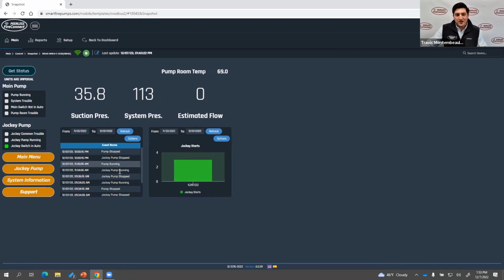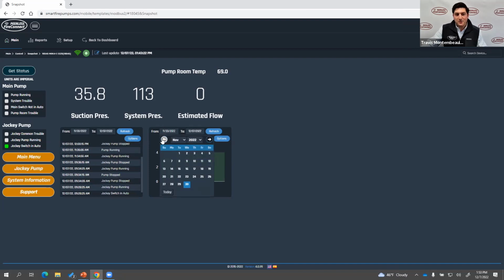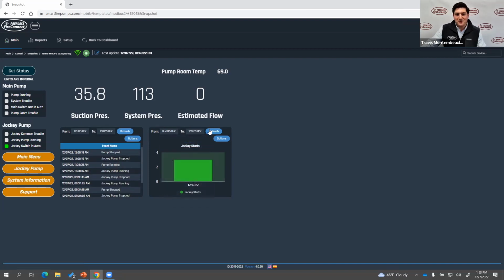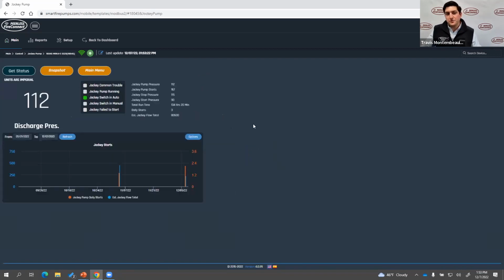Additionally, we've got the event log like you normally see. We've got the jockey pump log, and this is the demo one here in the office, which we've got on and off, but you would see over time your different flow rates or your different amounts of jockey starts effectively. So you're still getting that. And one of the features that we've added is giving you an estimate of how much water you're actually flowing through that jockey pump each day.